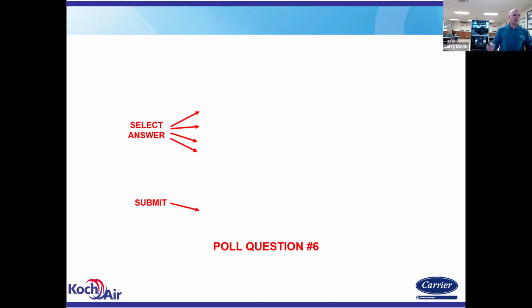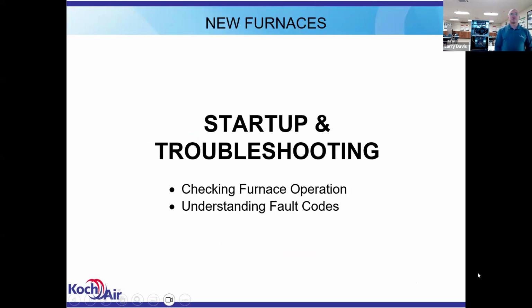You want to go through any or all of those steps, just making sure that in your cooling mode, you're checking it to that static pressure, and in your heating mode, you're verifying your temperature rise. All right. Good news is there's only 2 more of those questions left. Any questions before I move on to the startup and troubleshooting on setting the airflow?